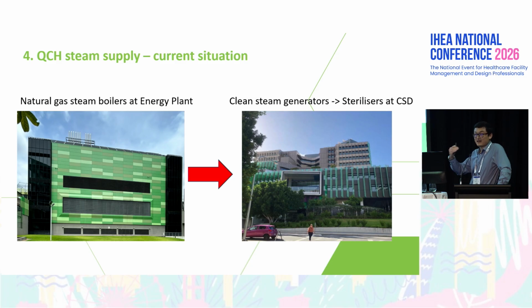Steam is our second largest natural gas use. Our natural gas use mostly happens here at the energy plant - that's our beautiful energy plant, and that's the hospital on the other side of the grassy knoll. The clean steam generators are on the 6th floor of this building. CSSD is the major steam use, and that's on level 5 of the hospital.